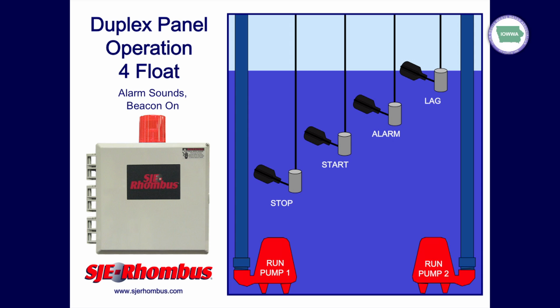You may not know you've got a problem until pump number 2 fails also, okay? By having the alarm float at or below the lag pump position, you're always going to know if you have a failure of a pump before it's a catastrophic situation. You would be able to tell that if you only had 3, right? That's correct. If you only had 3 and you use the floats, lag and alarm together, you won't signal that unless you see it.